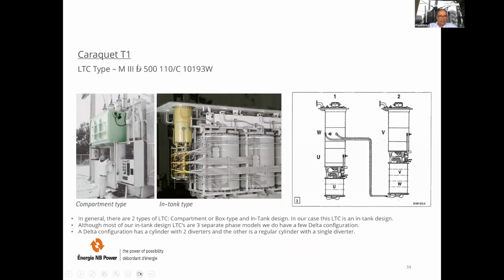So here, the LTC type. In general, there are two types of LTC: compartment or box type, and in-tank design. In our case, this LTC is an in-tank design, and although most of our in-tank design LTCs are three separate phase models, we do have a few in delta configuration. The delta configuration has a cylinder with two diverters, as you can see here on the right, and the other is a regular cylinder with a single diverter.